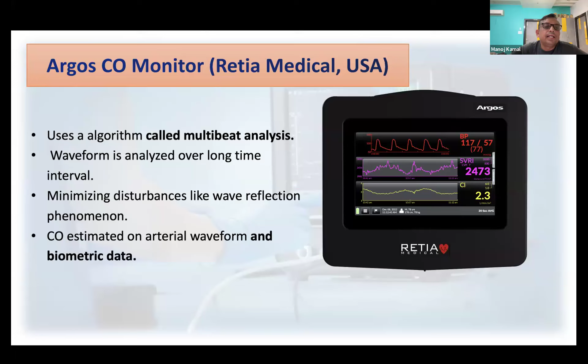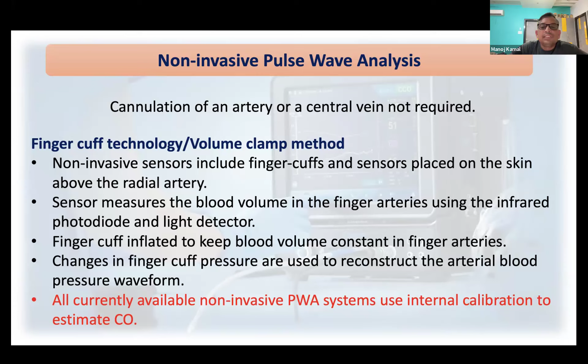For non-invasive monitoring, cannulation of an artery, peripheral artery, and central vein is not required. We use finger cuff technology or the volume clamp method. Non-invasive sensors include a finger cuff, or sensors placed on the skin above the radial artery. The sensor measures the blood volume in the finger artery using an infrared photodiode and light detector, and the finger cuff inflates to keep blood volume constant in the finger arteries. So changes in finger cuff pressure are used to reconstruct the arterial blood pressure waveform.